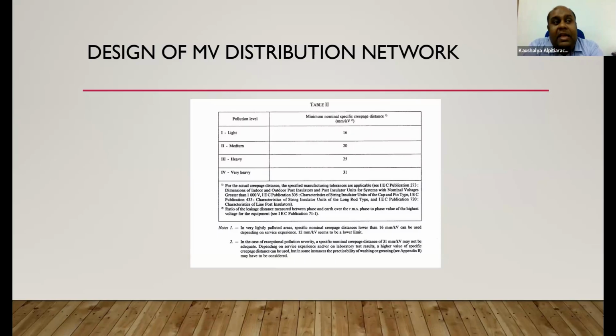So why is this important to the designer? Yes, the exposure of your medium voltage equipment to dust, dirt, or atmosphere, even though that's inside the building. If you go and see some installations, inside the medium voltage panel, or maybe the dry type transformer, you have a hell of a lot of dust there. Sometimes if that is near the sea, that is conductive, a salty dust. So the designer shall decide what creepage distance you're going to maintain and what level of pollution you're going to decide during the design stage.